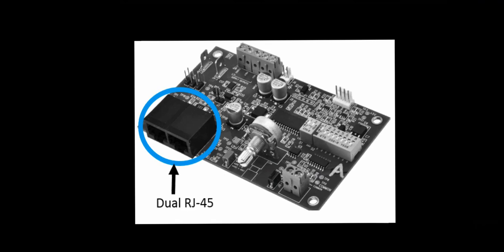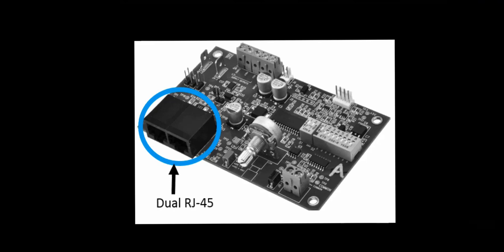The last control mode for the universal card is network control mode. In this mode, the units can communicate with the BAS through a Modbus RTU protocol. The universal control card is equipped with two RJ45 connectors, allowing them to be daisy chained to one another. The following points can be controlled or monitored over the network: unit start/stop, airflow setting as a 0 to 100 percent signal, motor speed, default airflow setting, default start/stop on power resume, and filter pressure drop when equipped with the continuous filter monitor.